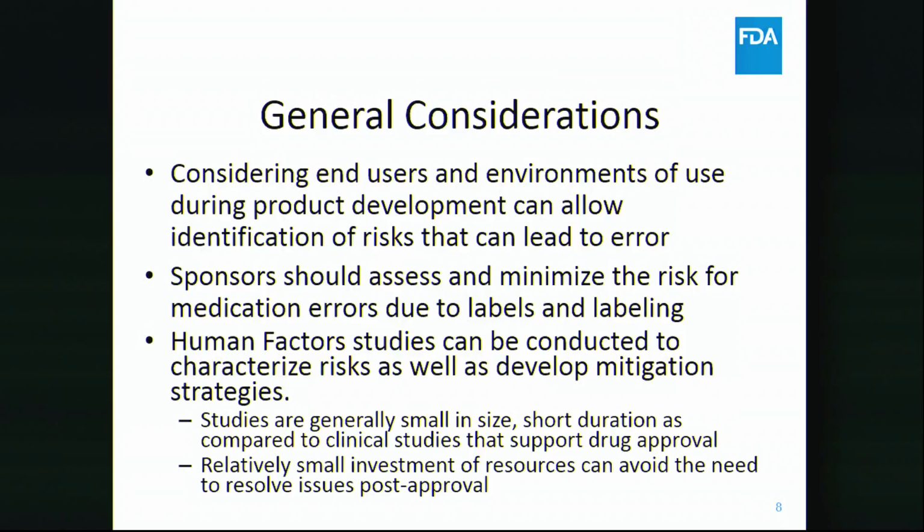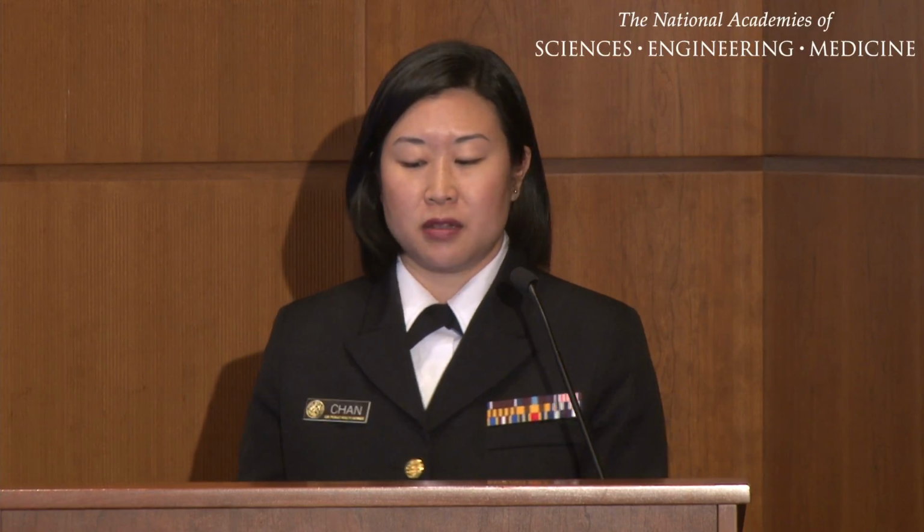And then we encourage the use of human factors and gathering data through human factors studies to help characterize the risks and develop risk mitigation strategies. And when we talk about a human factors study as compared to a clinical study, in contrast to clinical studies, you're talking about studies that are generally small in size and short in duration, as compared to these clinical studies.